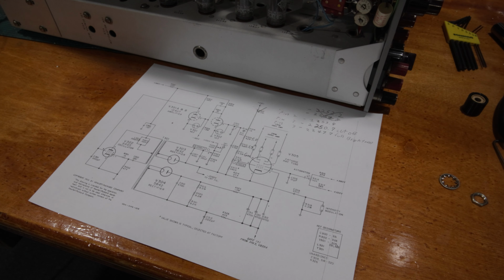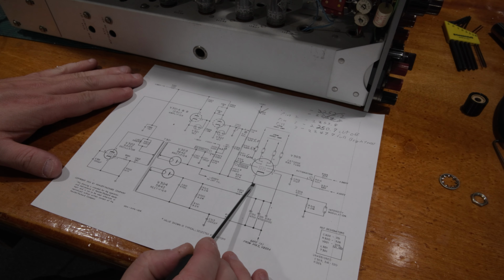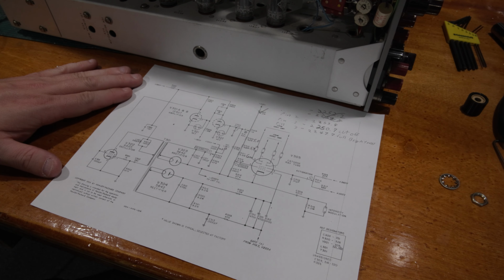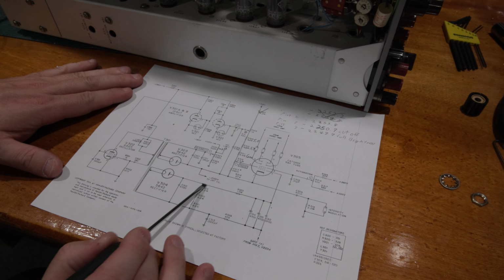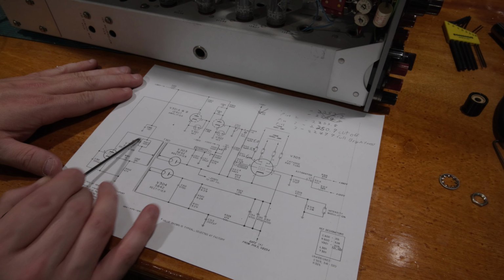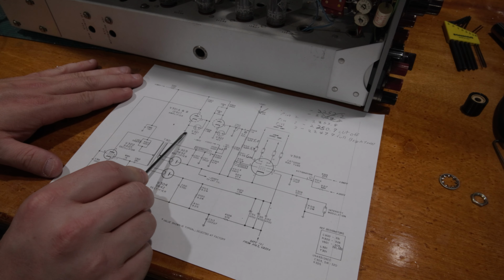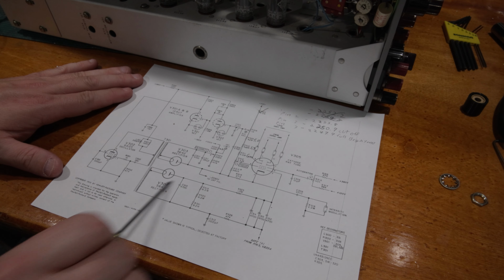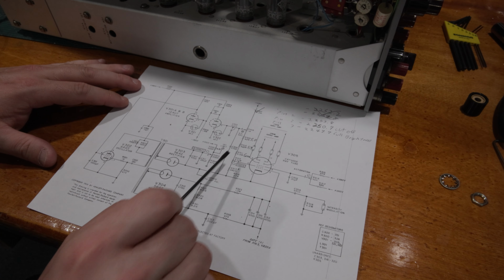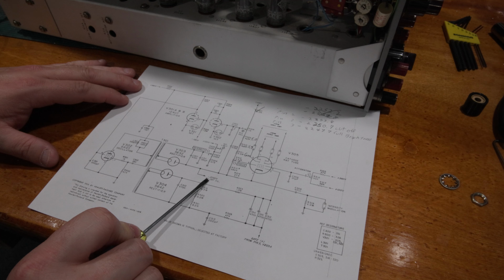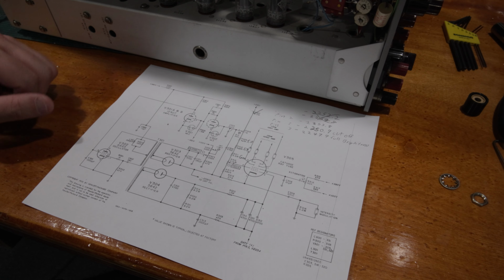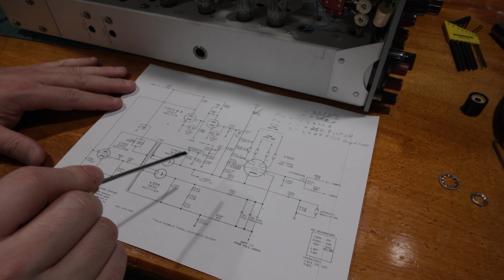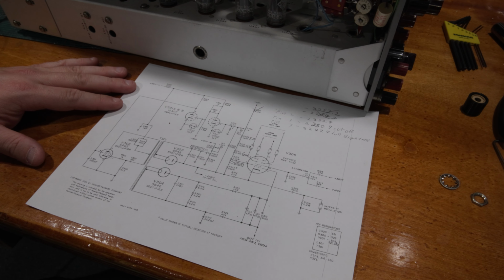There are two critical bias set points, and unlike a Tek scope that has a grid bias adjustment, this doesn't. It kind of self-balances. So we have the cathode, which is at negative 2,250 volts, and we were able to adjust that negative 2,250 volts. So I'm reasonably sure the oscillator's okay and the amplifier's okay. All this circuitry can pretty much be assumed okay, because I was able to adjust this, and I actually turned it way down and had plenty of adjustment left. That should have been a clue, almost bottoming out this control and having a bit too much voltage here.